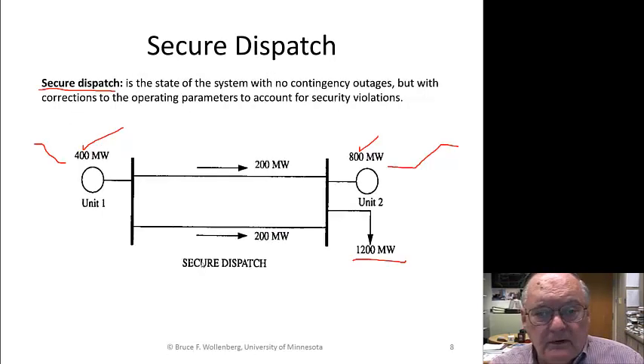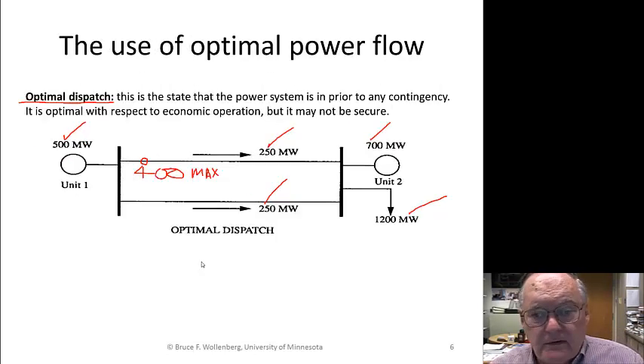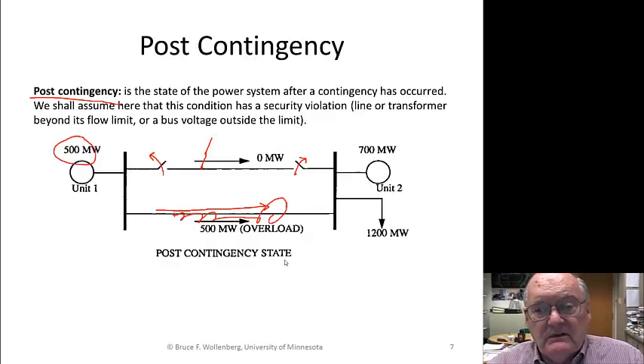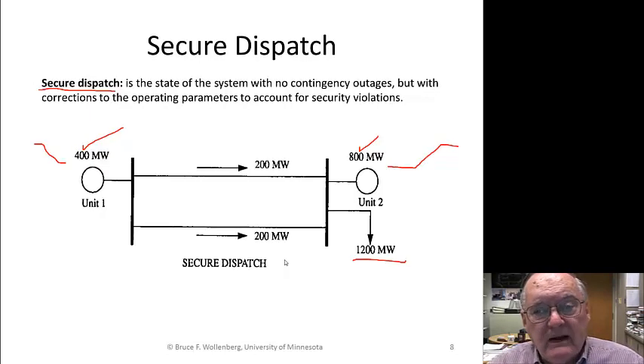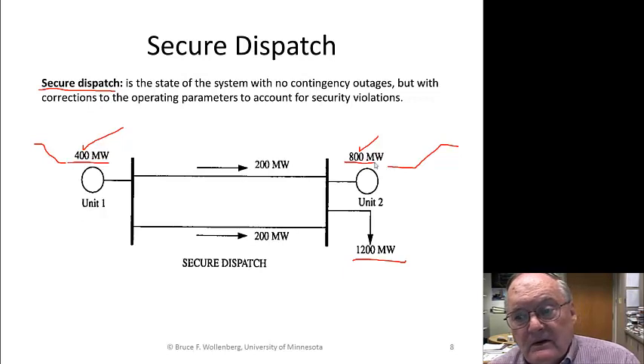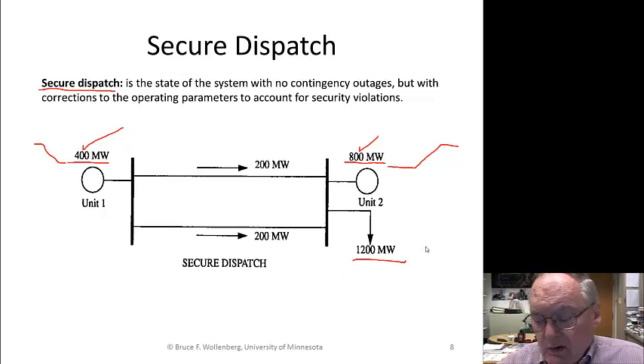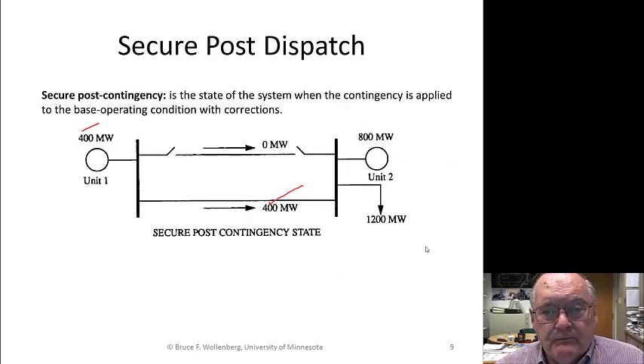For example, if I was doing the 500, this may be a very inexpensive source of generation, like a hydro plant or something, and I really want to buy as much as I can. They're willing to sell me 500, buy it all. It's cheaper than I can generate it. Unfortunately, the system is not secure. I've got to back off, and I've got to run this down and only buy 400 here and then 800 here. It's going to cost me more, but it is secure.